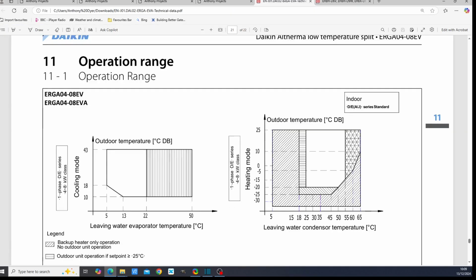Let's go here. This here is a diagram which shows you the different operating regimes. And anything below 18 degrees Celsius in terms of leaving water temperature is a backup heater mode only. Look here. So this is backup heater only operation, no outdoor unit operation. So for cold heating mediums, it will use the backup heater first before switching on your compressor. And that's not very efficient, of course, but it's also hard-coded. And even if you have set backup heater to restricted mode in your settings, it will still automatically use the backup heater in this instance.